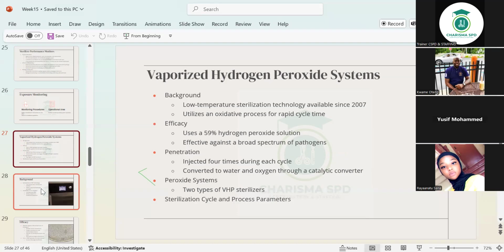All right. It's low temperature sterilization technology available since 2007. It utilizes an oxidative process, just like the hydrogen peroxide, the first one that we spoke about. The efficacy: it uses 59% hydrogen peroxide solution. The other one, which is the hydrogen peroxide, was from 59 to 95. You see the difference now? Mr. Obin, do you see the difference? It's all hydrogen, but one is vaporized, and the vaporized one is saying that it uses 59% hydrogen peroxide solution. And the original one that we spoke of uses between 59 to 95%. Okay, so if there's any difference, that's where the difference is showing up. The vaporized uses 59%. The regular one uses between 59 to 95.